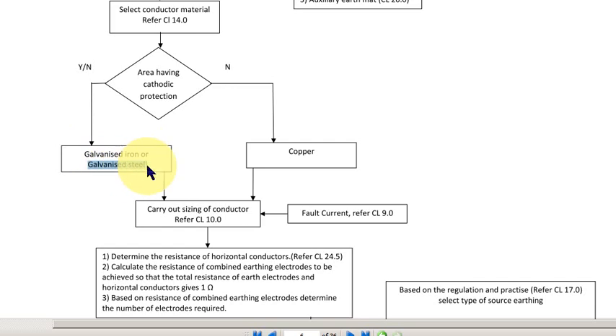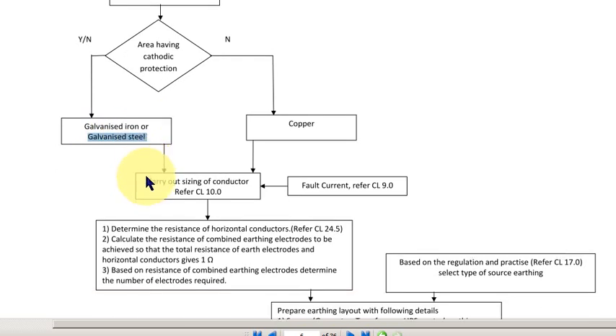Next is, you have to carry out the sizing of the conductor. Once you have decided the conductor type, then you have to do the sizing of the conductor. To size the earthing conductor, the input you need is the fault current.